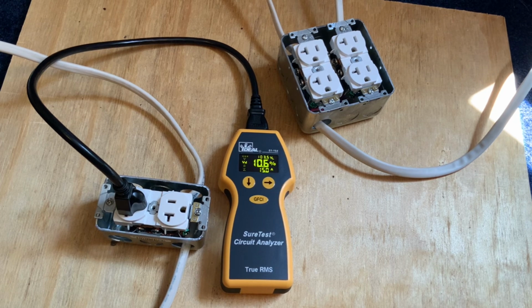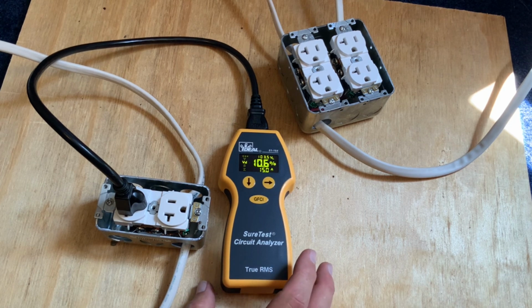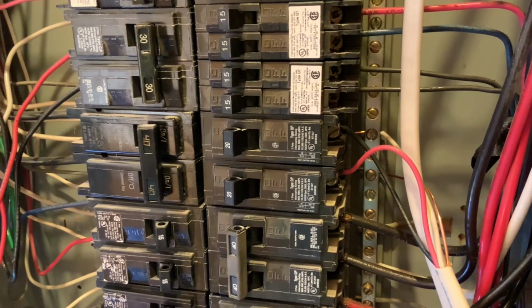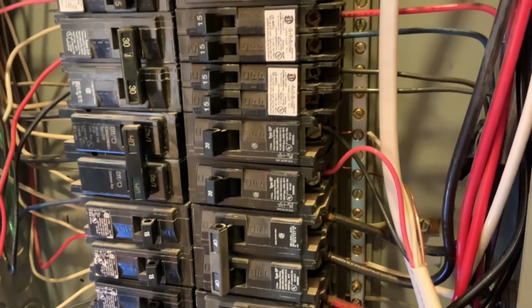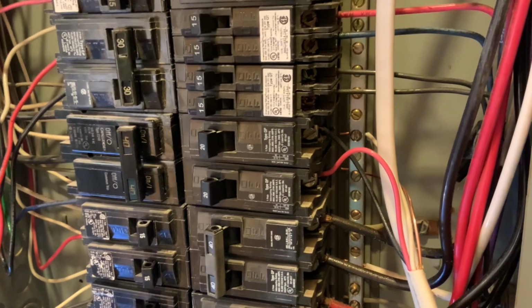But it does let you know that if you have something that is going to draw a lot of current, like a computer, when you plug into these outlets, you could have a significant voltage drop that gets that voltage down to 103, 105 volts. And some computers might have trouble working at 103, 105 volts. So it lets you test outlets in your house to find out areas where equipment may have difficulty running on those outlets. The ground to neutral voltage measurement can be very helpful in identifying issues with balanced and unbalanced grounds.